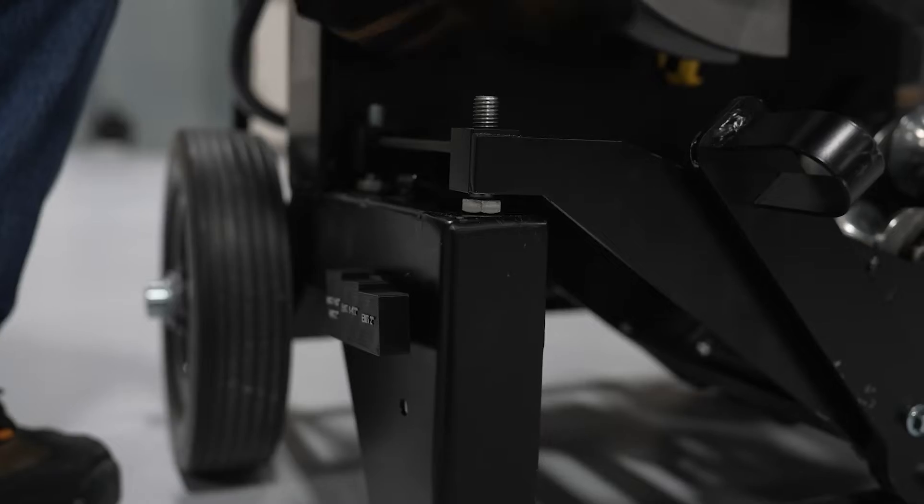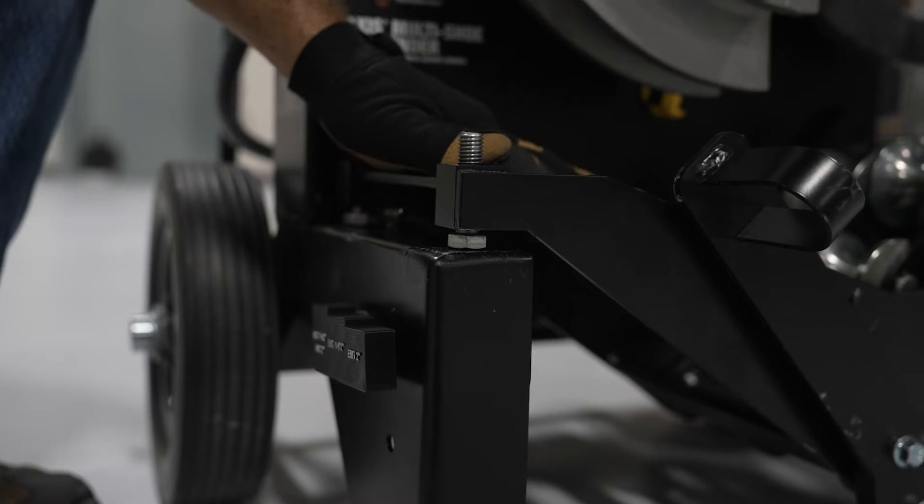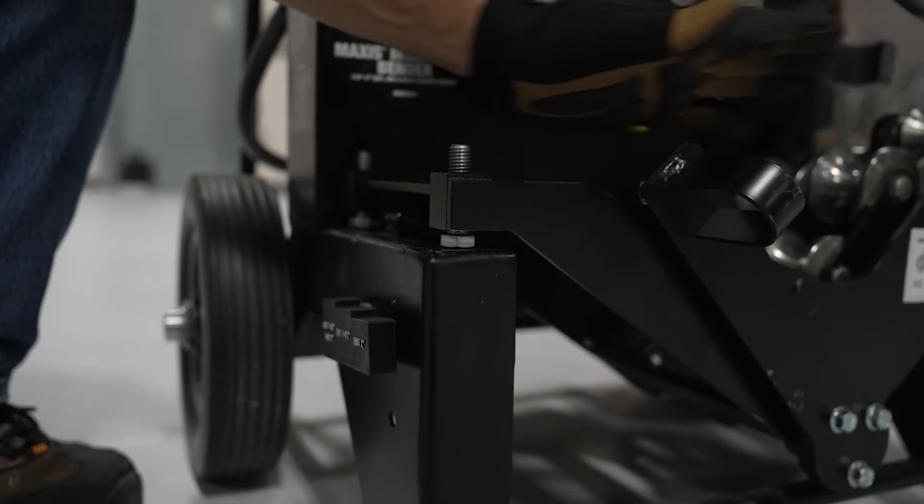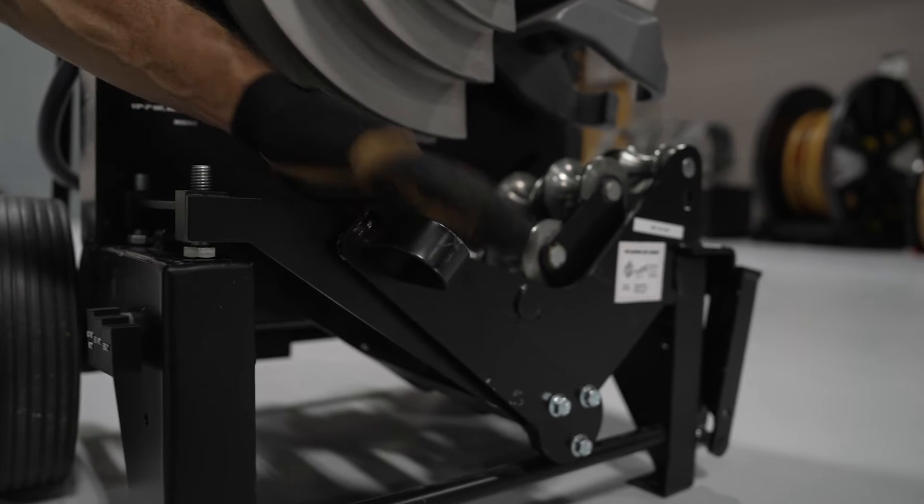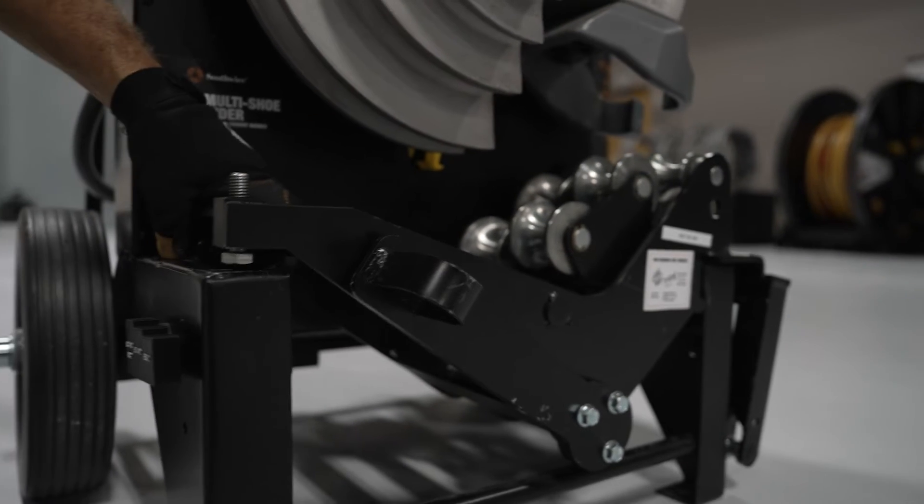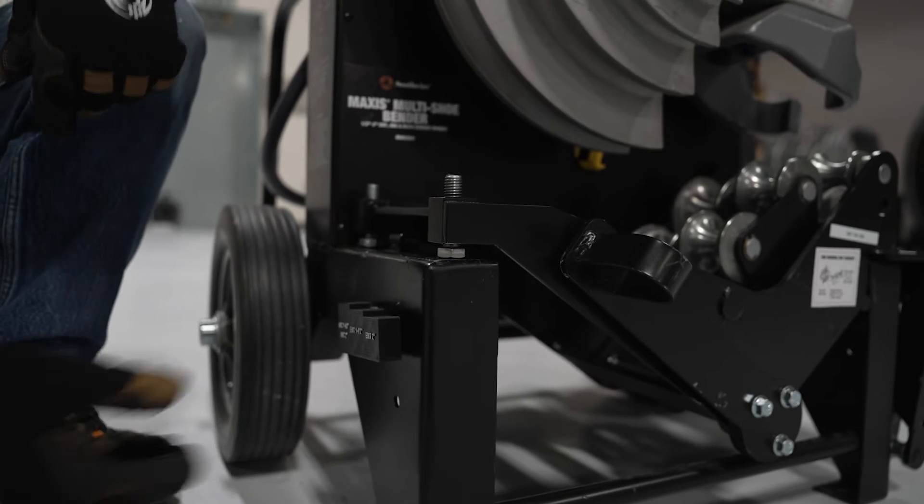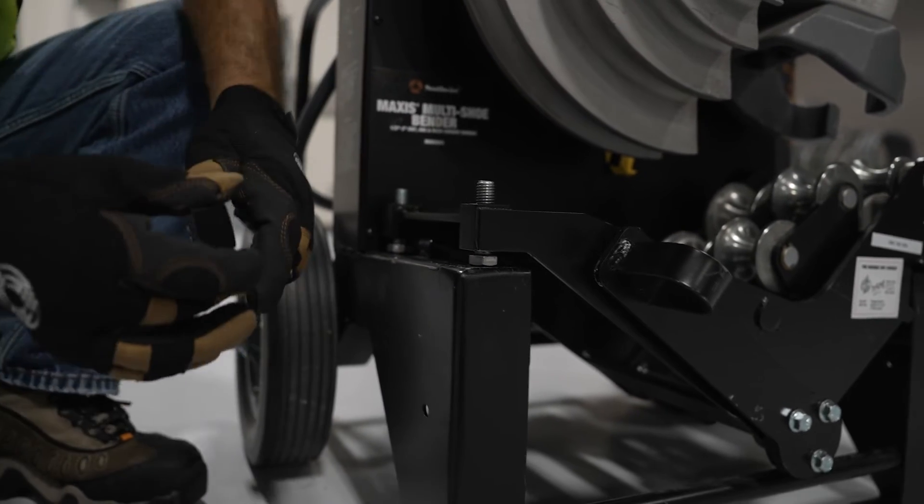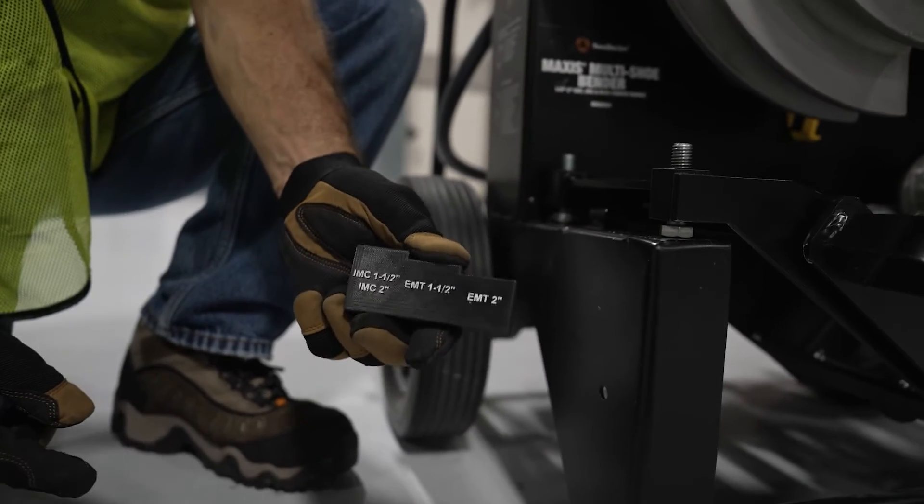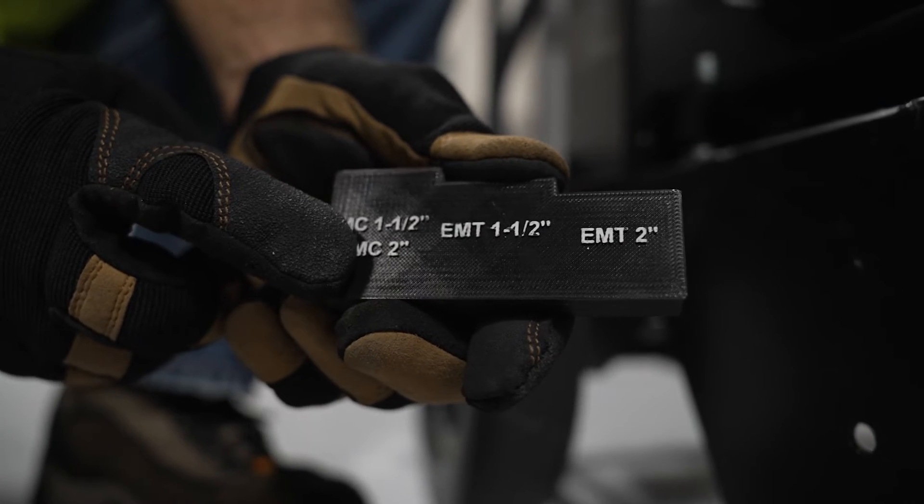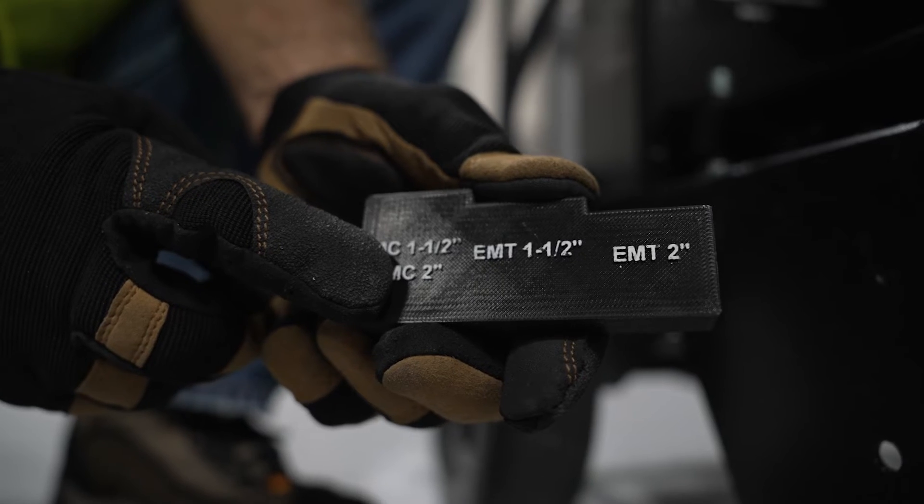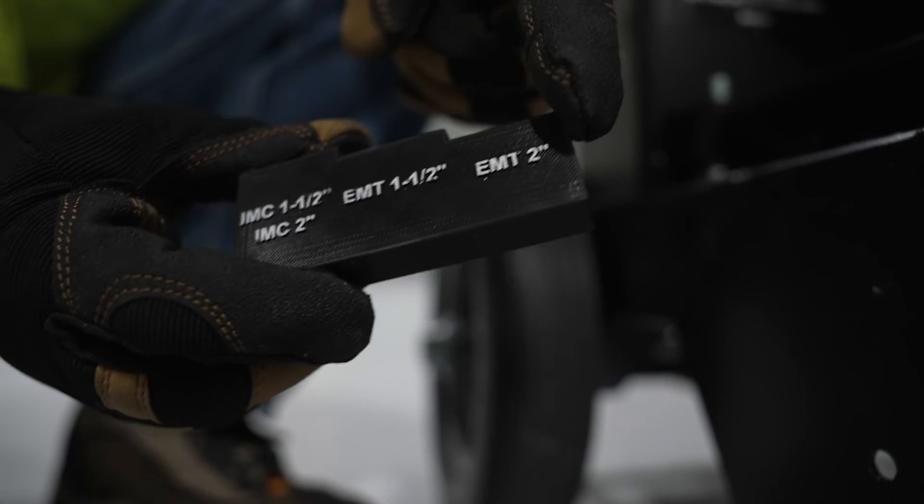Now if you are bending inch and a half or two-inch EMT conduit, you'll be using the pressure pedal, and now is a good time to preset the height of the pressure rollers. Your MSB2000 was shipped from the factory with an innovative pressure roller gauge tool only available from Southwire. We've provided this tool to reduce the guesswork when it comes to adjusting the pressure roller height.